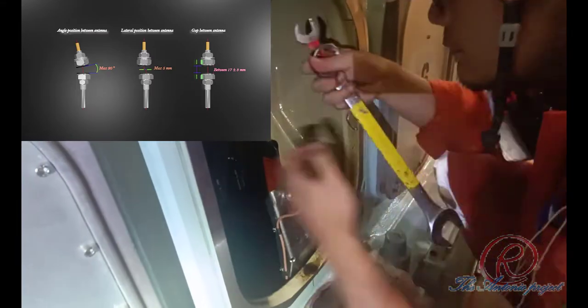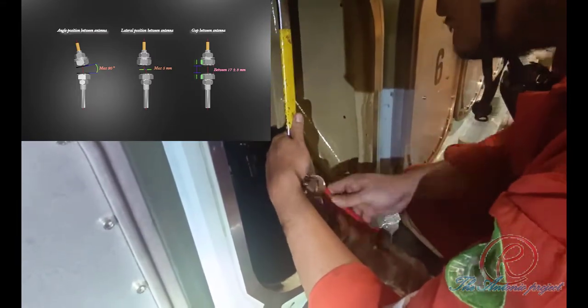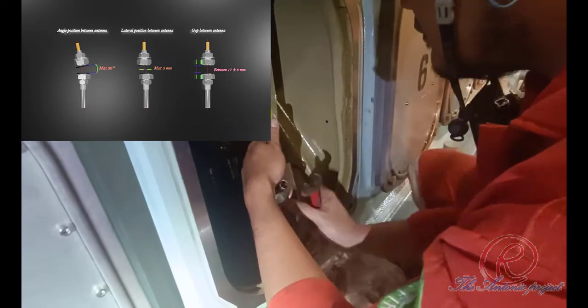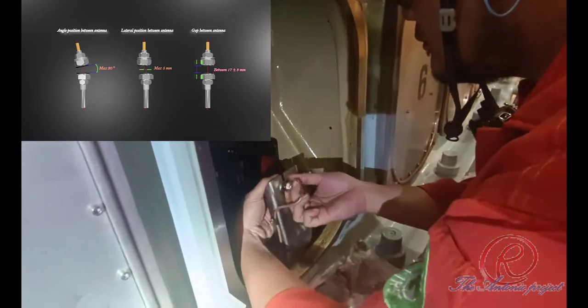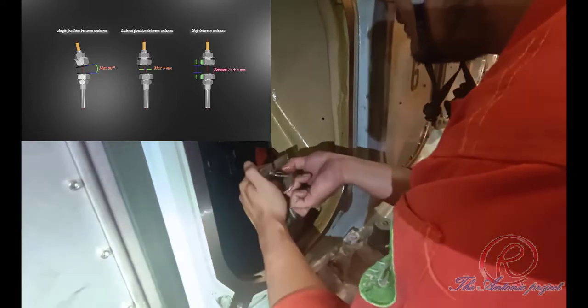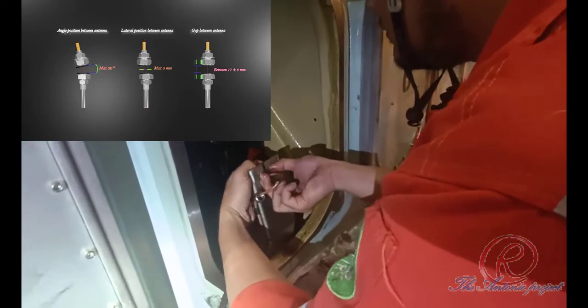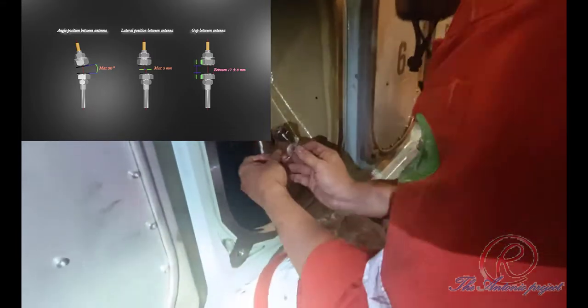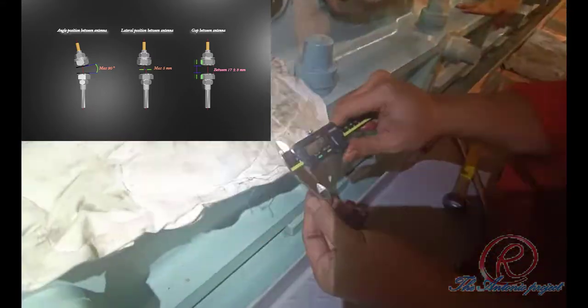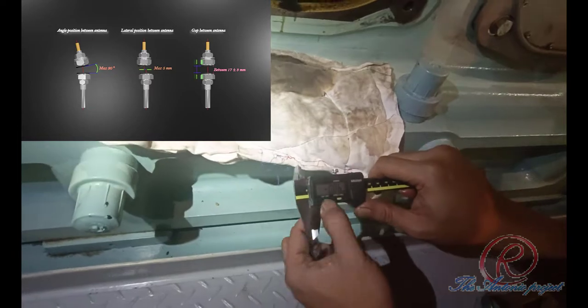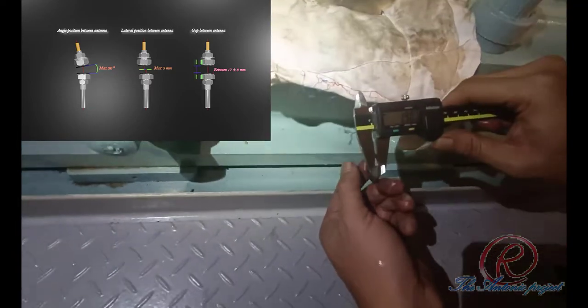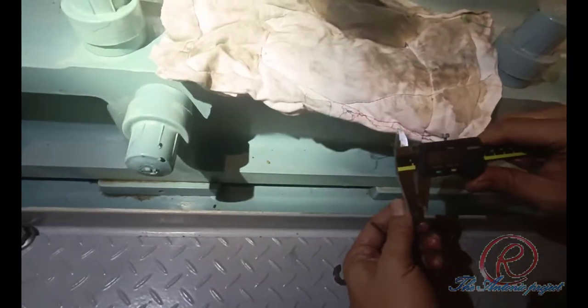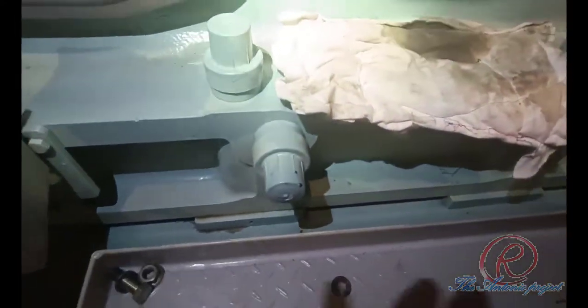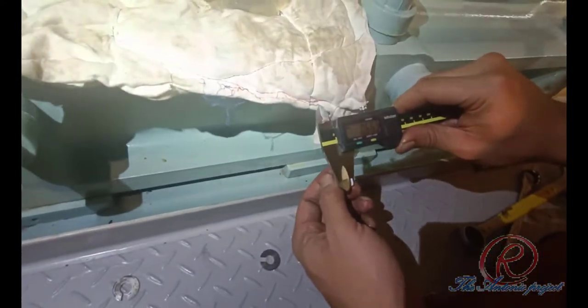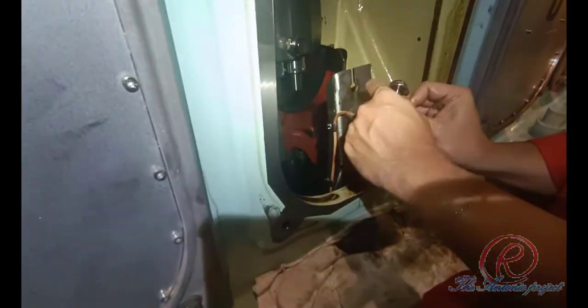Due to this doubtful condition for sensor number 7, and the possibility that the sensor is malfunctioning, we carry out an investigation by measuring the gap between the sensor and the stationary antenna, and found that the gap is 13.8 mm, less than the standard 17 plus minus 3 mm. Therefore, it is necessary to adjust the gap. By replacing the existing spacer from 1.9 mm to 0.7 mm, it is expected that the gap will increase from 13.8 mm to 15 mm.